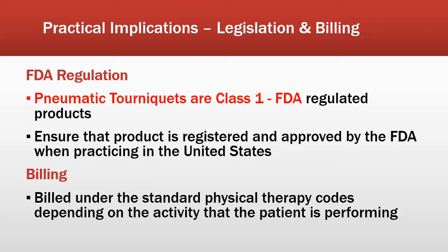However, in speaking to the FDA directly just last week, that was as of April 2019, their representative said that given the fact that other pneumatic cuffs with the intended utilization of restricting blood flow for training outside of surgery have registered, any other product that is stated to be a medical device or to be used in the medical industry or setting needs to also register.